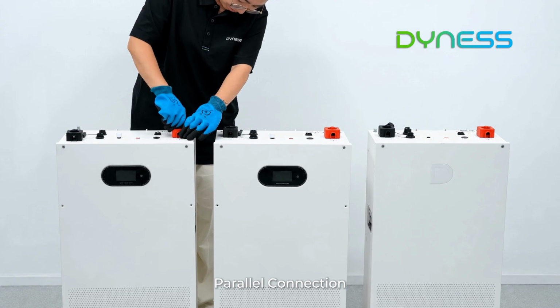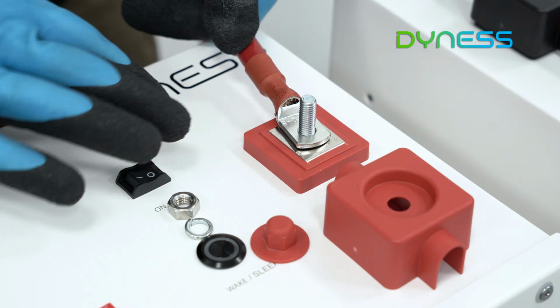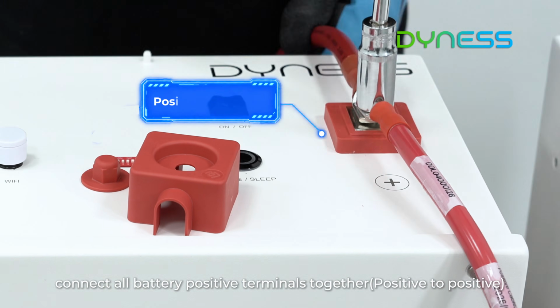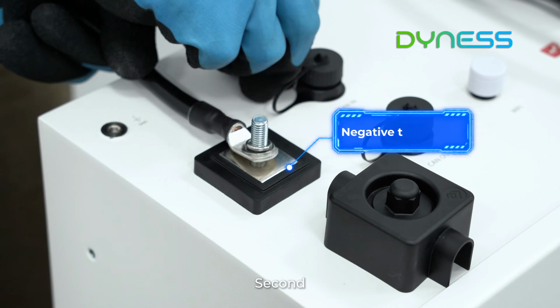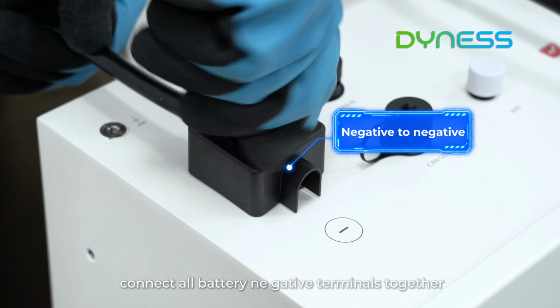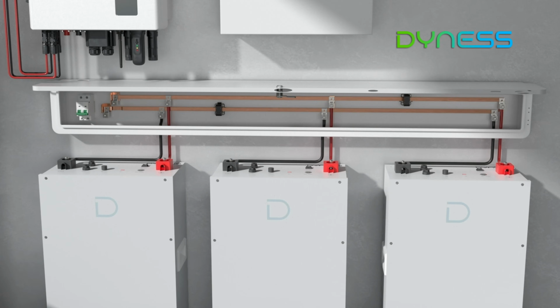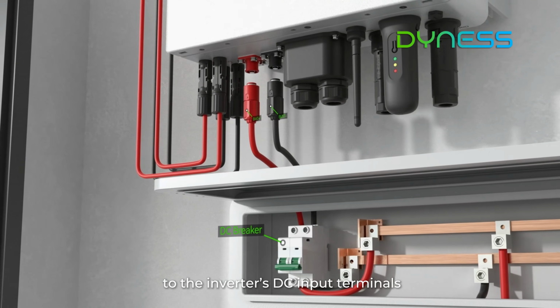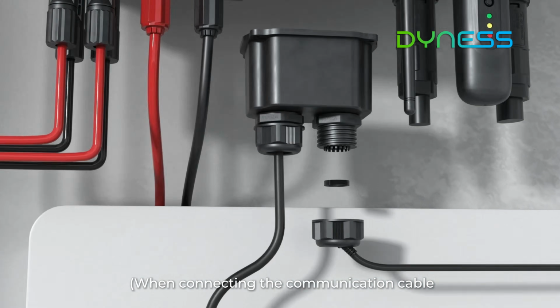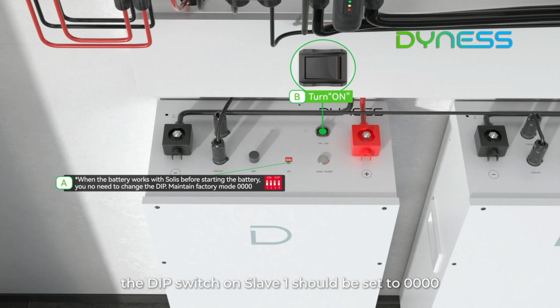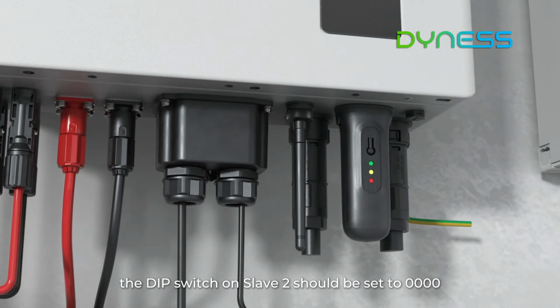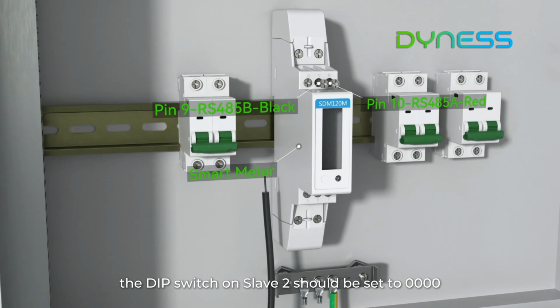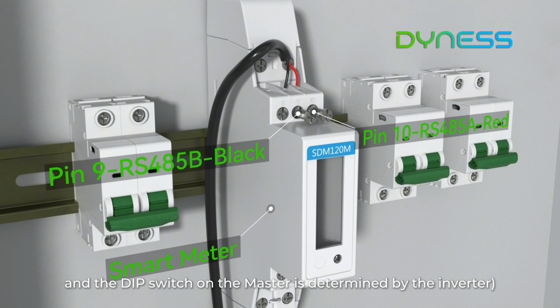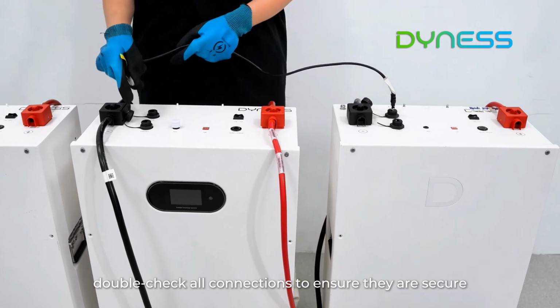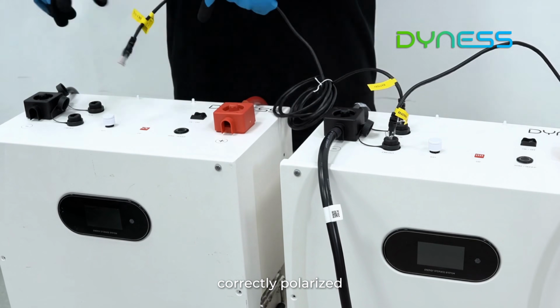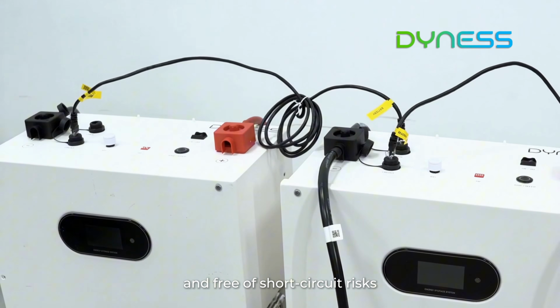Step 2. Parallel connection. Now proceed with the parallel connection. First, connect all battery positive terminals together, positive to positive. Second, connect all battery negative terminals together, negative to negative. Third, connect the combined positive and negative bus bars to the inverter's DC input terminals. When connecting the communication cable, the DIP switch on slave 1 should be set to 4 zeros, the DIP switch on slave 2 should be set to 4 zeros, and the DIP switch on the master is determined by the inverter. Finally, double-check all connections to ensure they are secure, correctly polarized, and free of short-circuit risks.